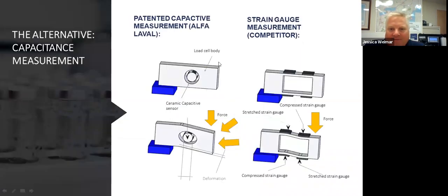So this is really the meat and potatoes of the presentation right here, folks. If you look to the right, we just talked about this, and this is a great graphic representation of what's going on in a strain gauge load cell. If you can envision, this is your beam, we call it. This is your fixed end here on the bottom left, and this is your force as your weight is applied to it. This beam frame is deflected. As I mentioned to you earlier, you'll see these strain gauge elements which are attached, and the four of them form what's called that Wheatstone bridge circuit. They're all used in concert to measure resistance change as the frame is bent.